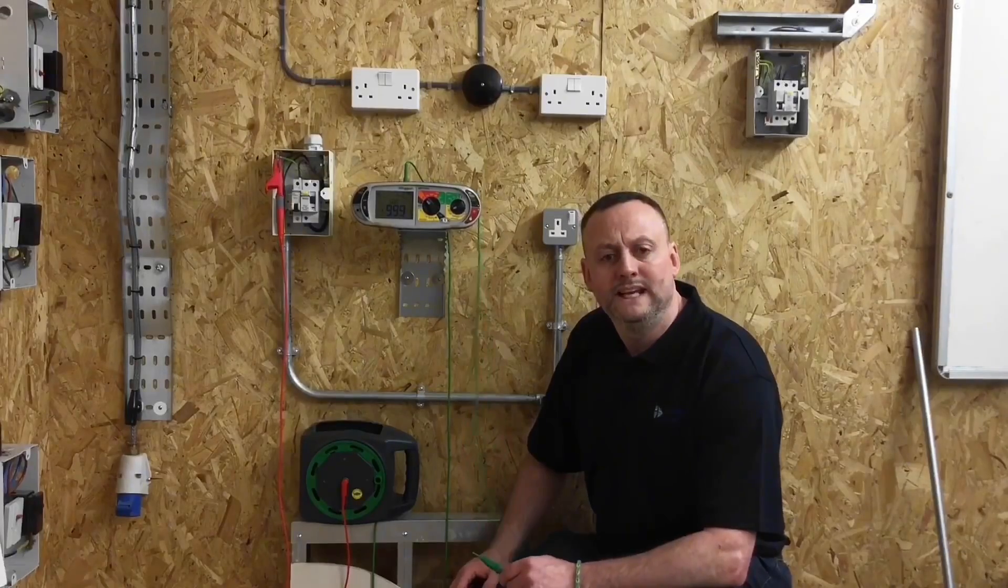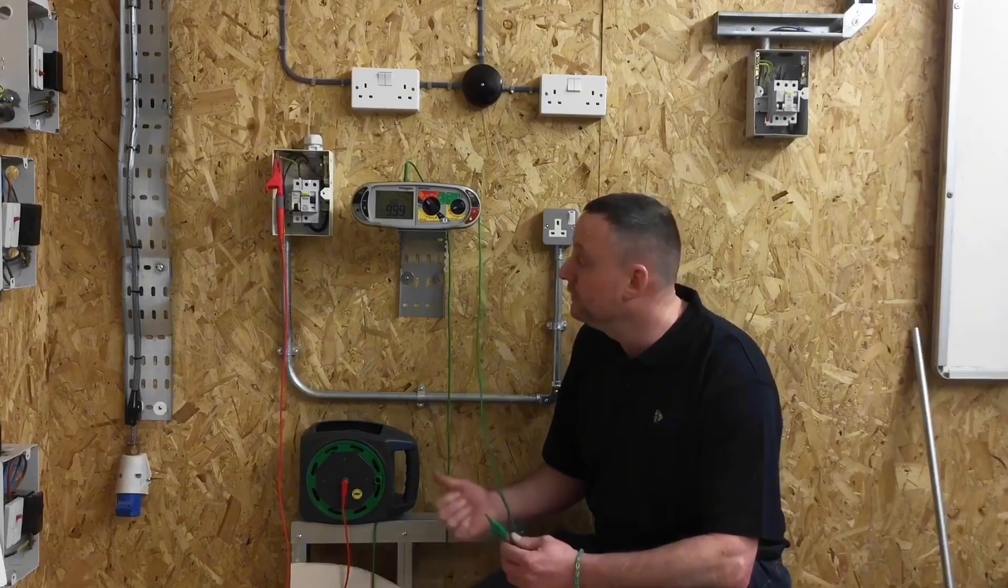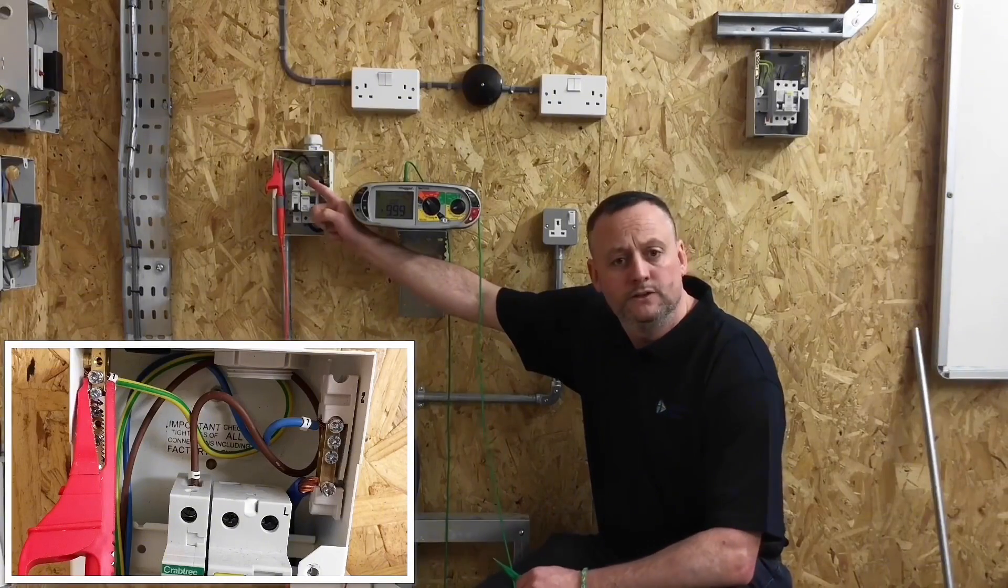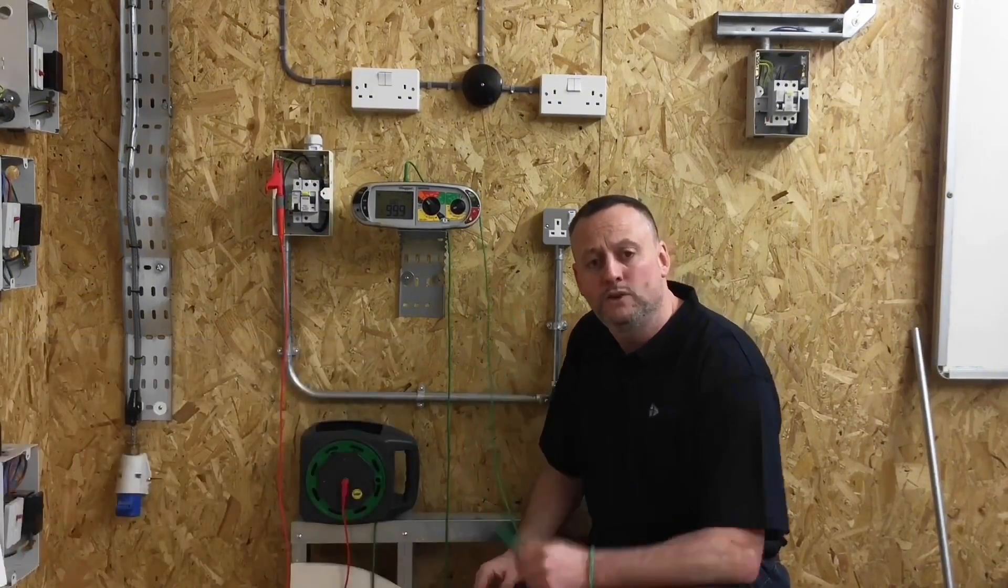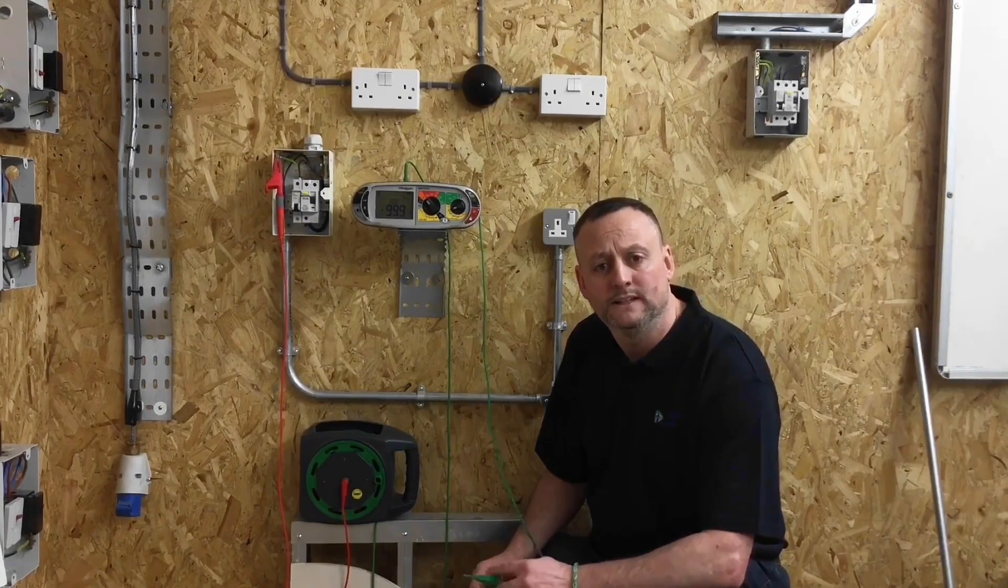I've set up my long wandering lead. I still get my learners to set up the long wandering lead, even though they could use the two very short leads in the tester, because the job is very small. I've connected one end of it to the earth bar. I've zeroed out the leads, and I've got the other probe, which I can go around and probe onto the exposed conductive parts to prove they're connected to earth.